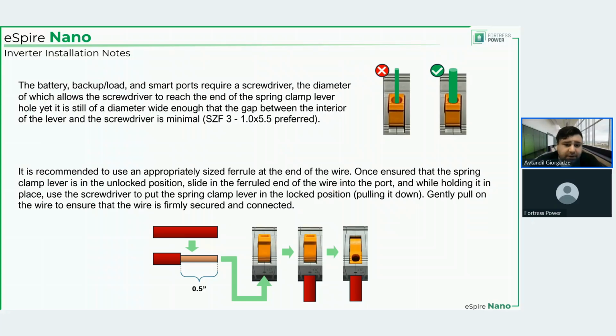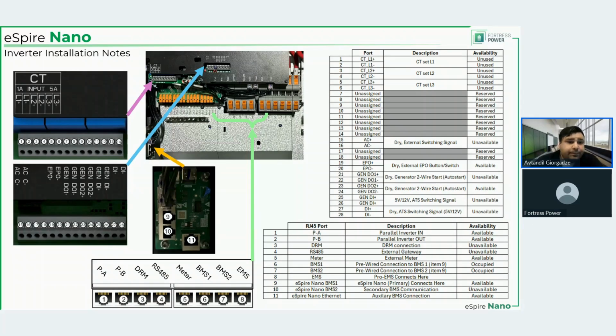So we were talking about the power ports. Now let's talk about communication ports and signal communication ports. There are multiple signal communication ports, but some of them are reserved, some of them are not to be used in the applications that we allow to use the system for. The important ones that I really want to highlight on the signal communication side would be EPO plus and EPO minus, a dry external EPO button switch. As I said before, you have an EPO button on the inverter itself. You also have, and you will see that later, an EPO button on the battery itself as well.